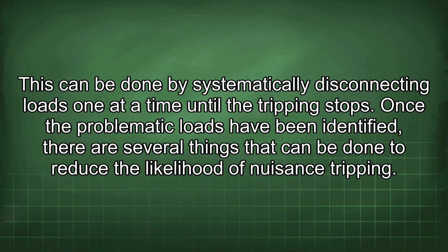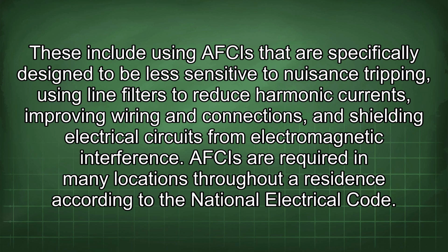Once the problematic loads have been identified, there are several things that can be done to reduce the likelihood of nuisance tripping. These include using AFCIs that are specifically designed to be less sensitive to nuisance tripping, using line filters to reduce harmonic currents, improving wiring and connections, and shielding electrical circuits from electromagnetic interference.